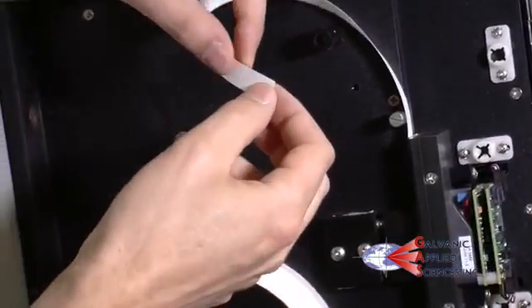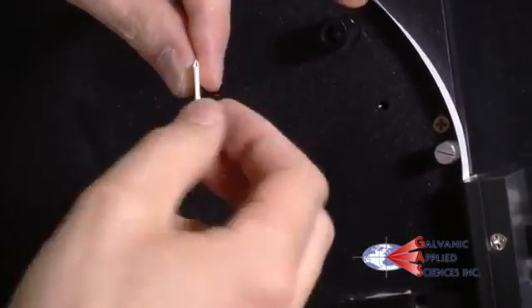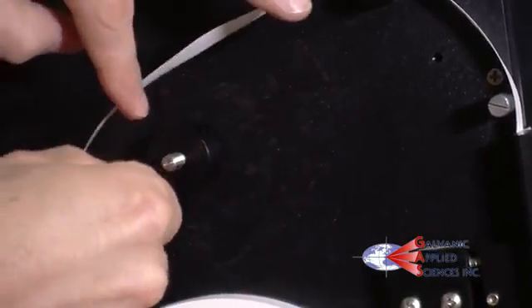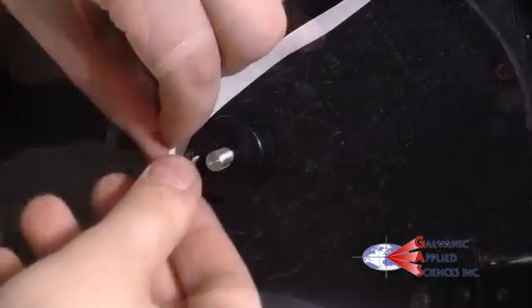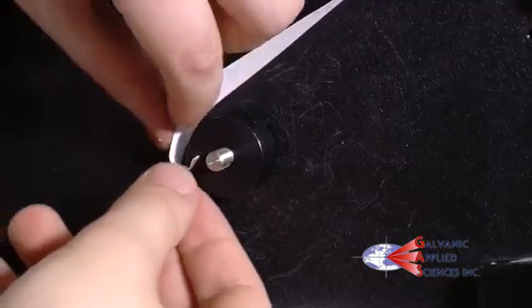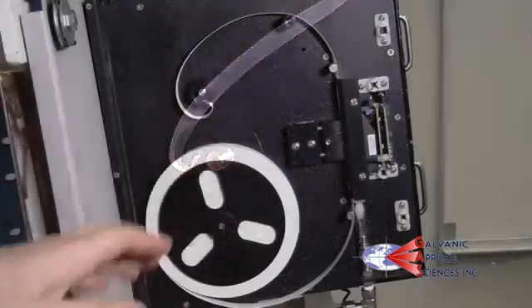Once the tape is guided through, take about 1 cm of tape, fold it over and insert it into the slot on the take up hub. Take up slack by winding back the lower spool.